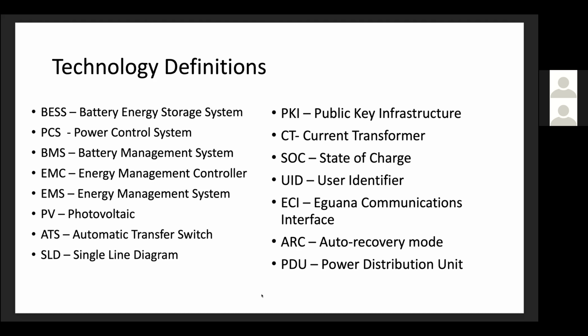But basically, the Evolve platform allows for auto recovery of any significantly depleted battery modules without having to pull it off the wall to send it back to the manufacturer for recovery, or no need for a special external charging device to recover any critically depleted batteries. As long as there is grid voltage, the system will auto recover any battery modules that can be recovered, which is a really nice feature. The PDU is the power distribution unit, basically just a metering circuit within the EMC. It's got a built-in meter in there.